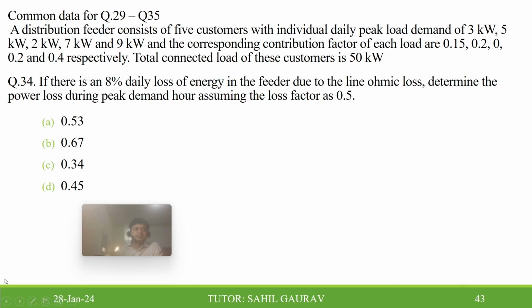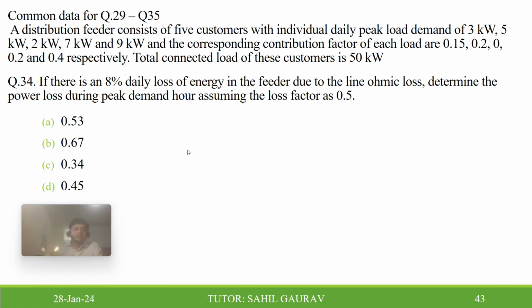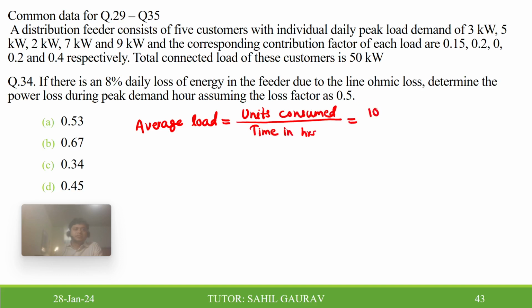Now the next problem is that if there is 8% daily loss of energy in the feeder due to the line ohmic loss, determine the power loss during peak demand hour assuming the loss factor as 0.5. So for loss factor also we have to calculate the average power loss. So average, first we are going to calculate this average load. Units consumed divided by time in hour. Time in hours, so it is 100 kilowatt hour divided by 24 hour. So it will give you 4.167 kilowatt.